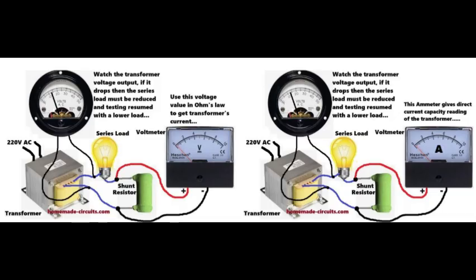How it works. We connect the shunt resistor in series with the load at the secondary side of the transformer. We connect the ammeter across the shunt resistor, or we measure voltage drop across the shunt and calculate current using Ohm's law. I equals V shunt divided by R shunt. Now we slowly start increasing the load, like connecting one bulb first, then two bulbs, etc. At each step, we measure. Voltage drop across shunt gives us current.